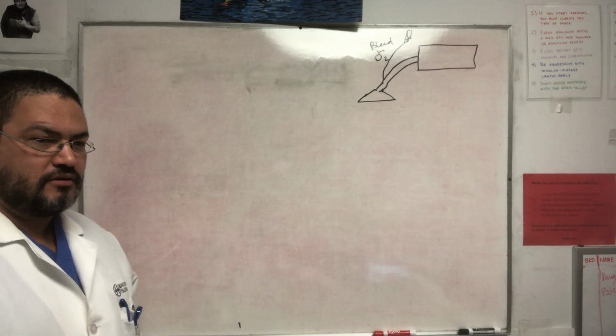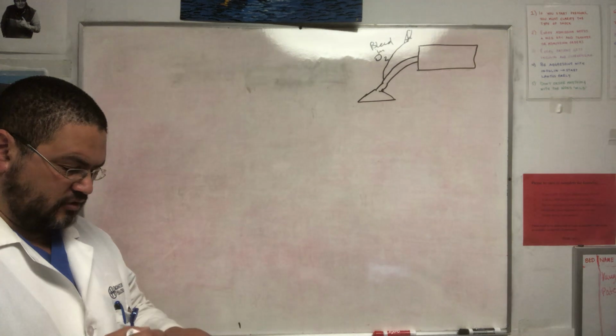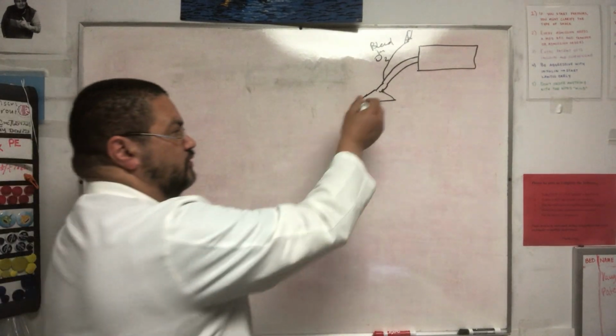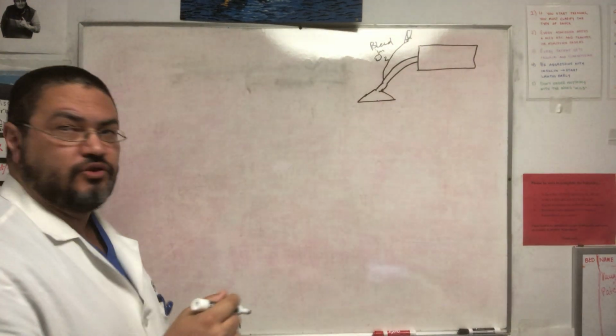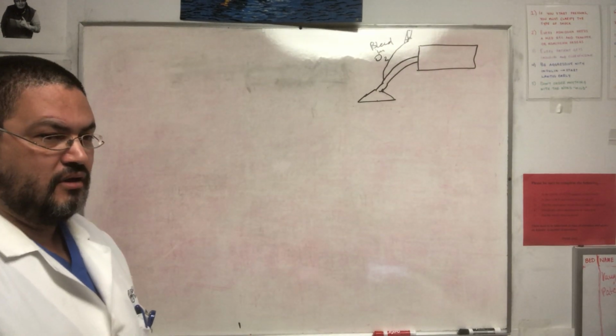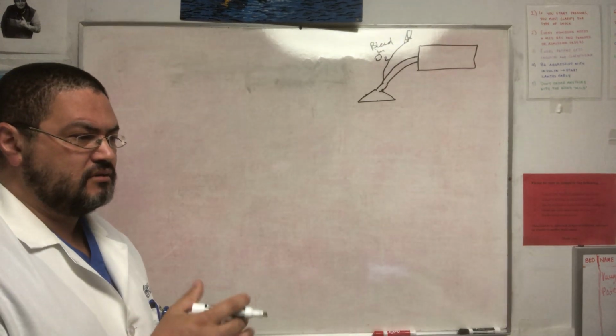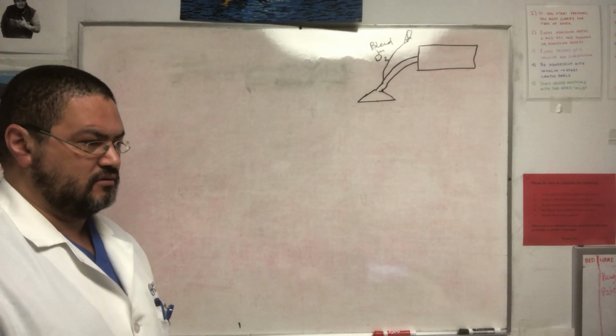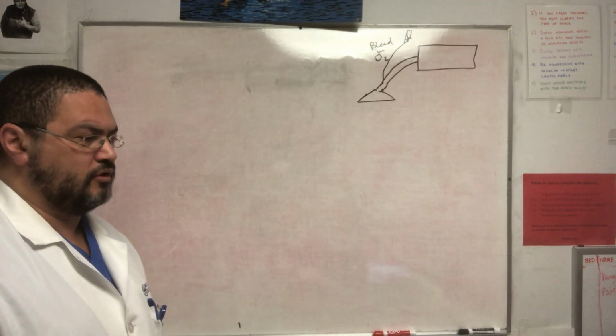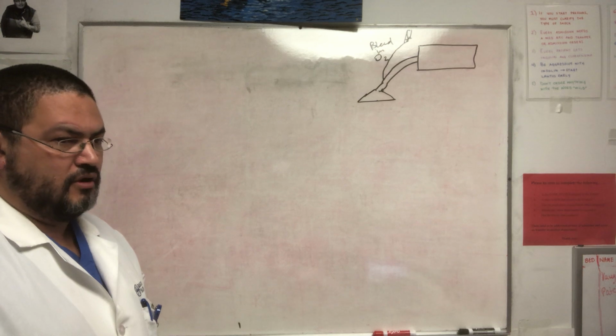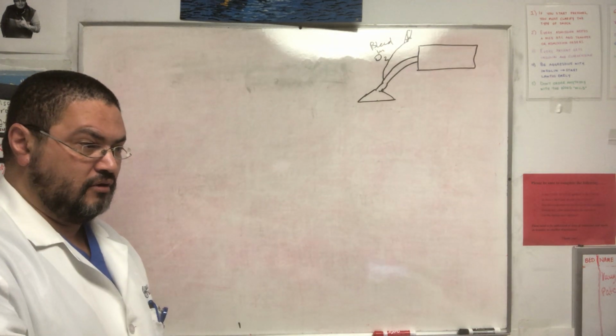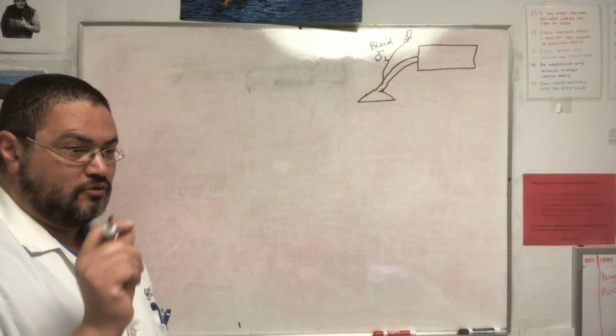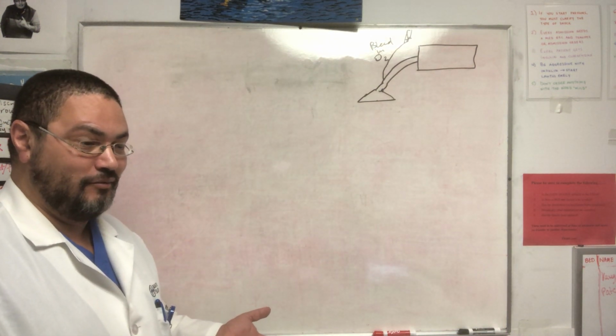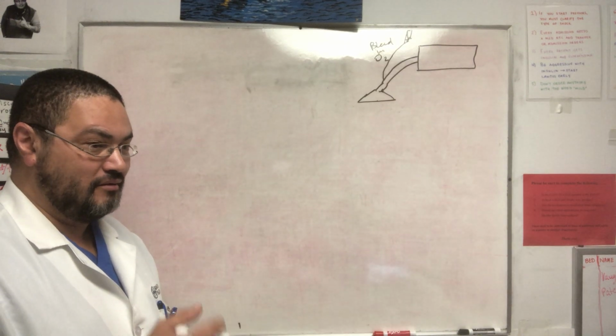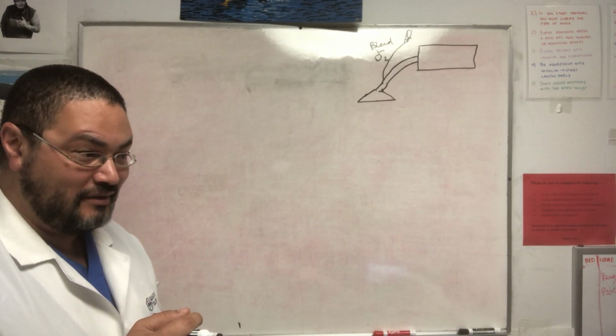Now, the bleed-in oxygen is a scam. If you imagine the FiO2 here for the patient, let's say a 2 liter nasal cannula, right? The flow here, the least flow is probably 30 to 40 liters, usually 40 or more. But let's assume it's 30 liters of flow. So you're giving 30 liters per minute of flow, and then 2 liters of 100% oxygen. What do you think we're raising the FiO2 by? From 21% to 22% maybe? That's the only thing this bleed-in oxygen does.